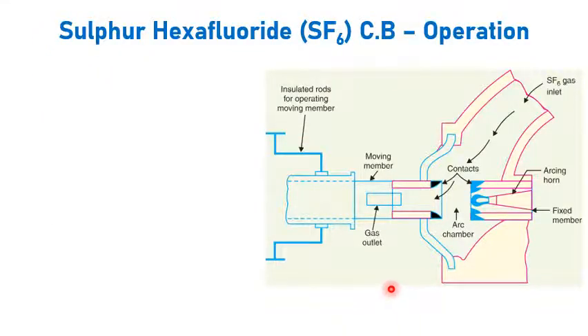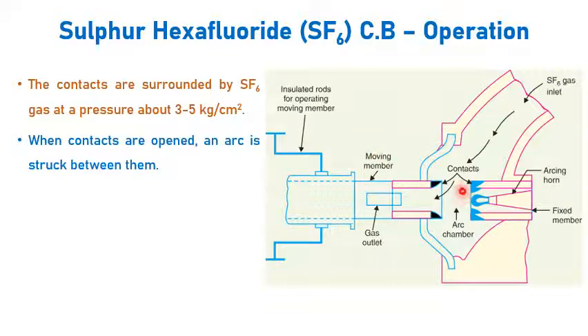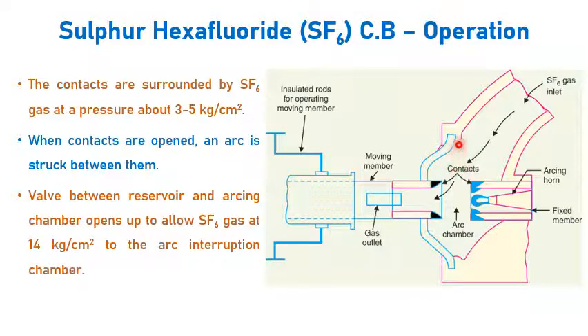Let us see the operation of the SF6 circuit breaker. During a no-fault condition, both contacts are in the closed position and are surrounded by SF6 gas at a pressure of 3 to 5 kg per centimeter square. When contacts are opened and an arc is struck between the fixed and moving contacts, a valve between the reservoir and the arcing chamber opens and SF6 gas at 14 kg per centimeter square enters into the arcing chamber.